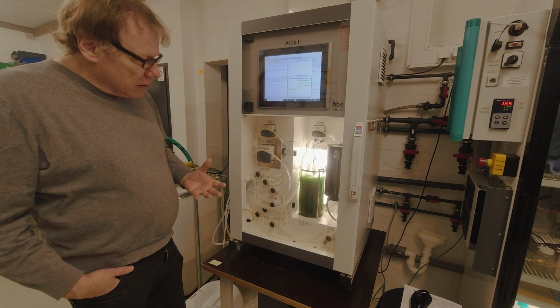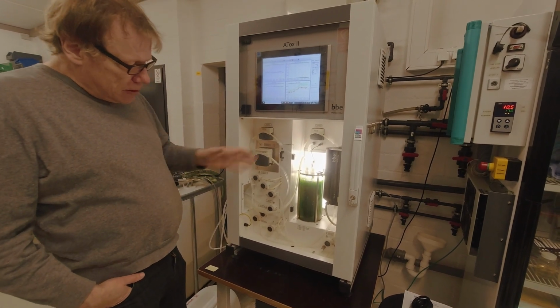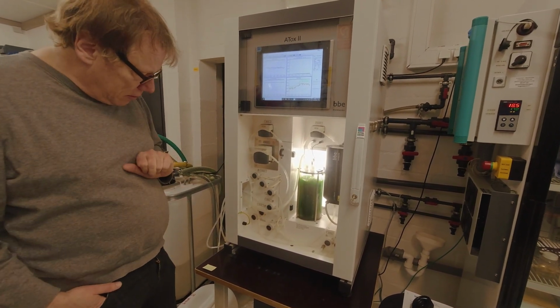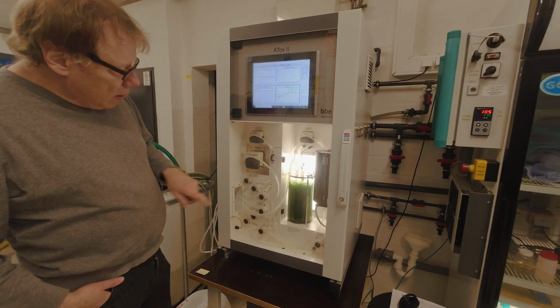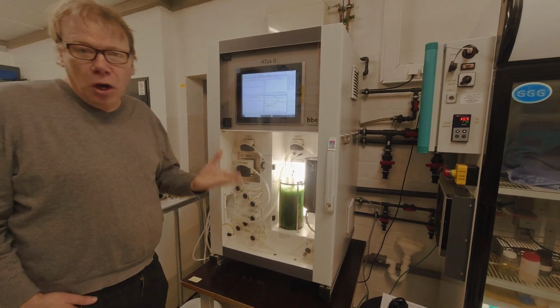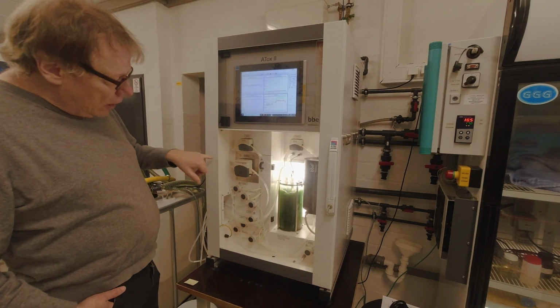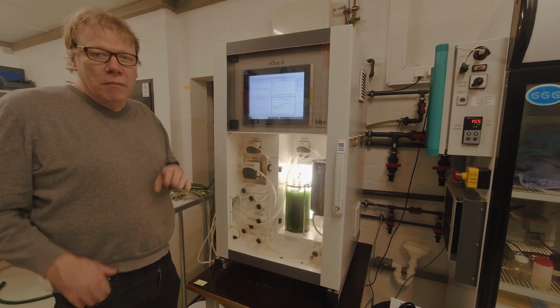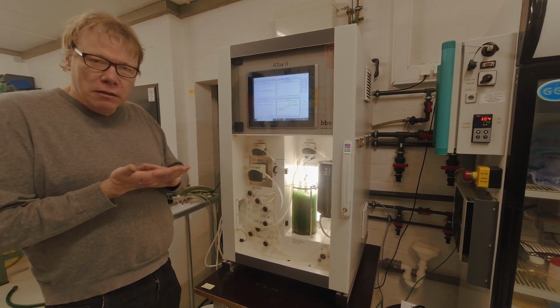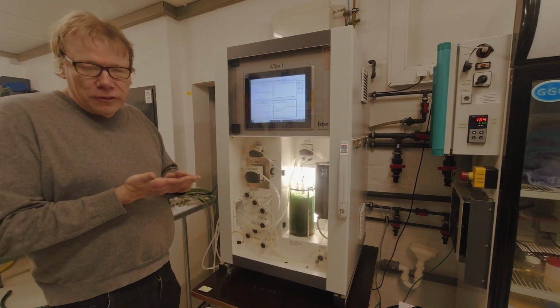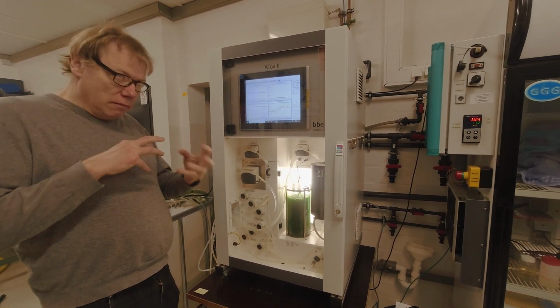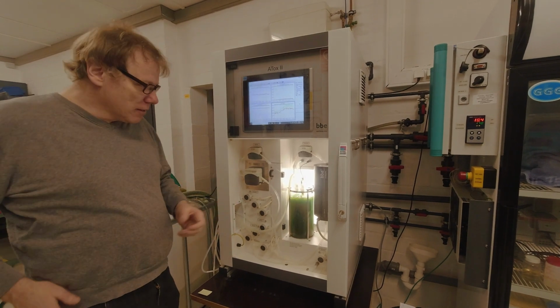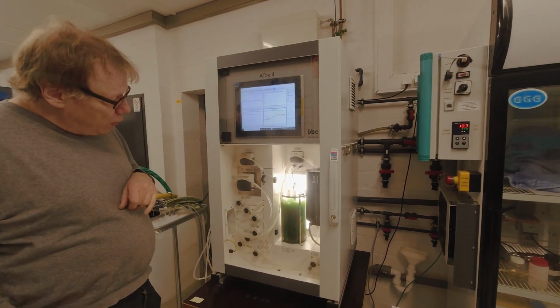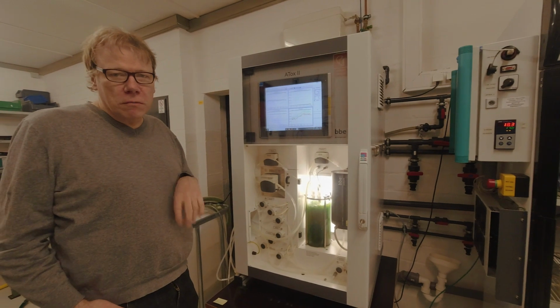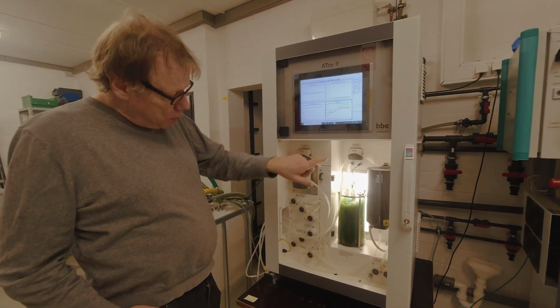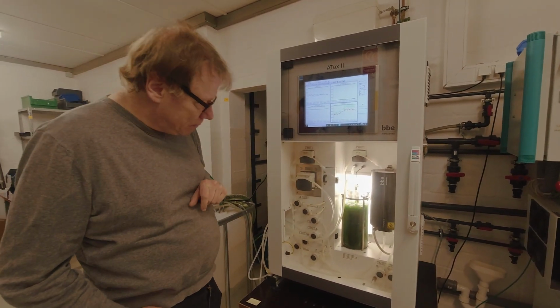So maintenance mainly is cleaning and replacing the nutrients, and also from time to time, but only monthly, you have to exchange the pump tubes, because the pump tubes will be sheared after some time. They will get weaker, they pump less, so for precision pumping you need to replace the pump tubes in all these 3 pumps.